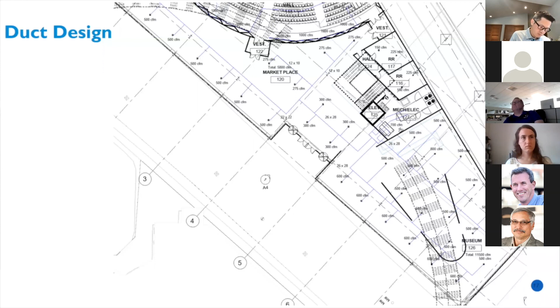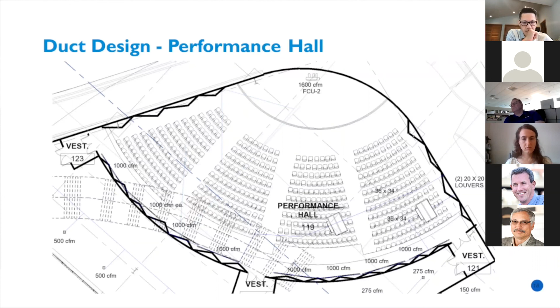For the performance hall, we have supply diffusers located on the floor at the back of the hall, pushing cold air forward towards the stage and up where it gets returned into a plenum. Two air handling units cool the audience, seen in the two right sections of seating, and are spaced apart to minimize noise. They receive fresh air from two louvers. Also, the stage is cooled separately by a fan coil unit with open return to handle the high heat load space.